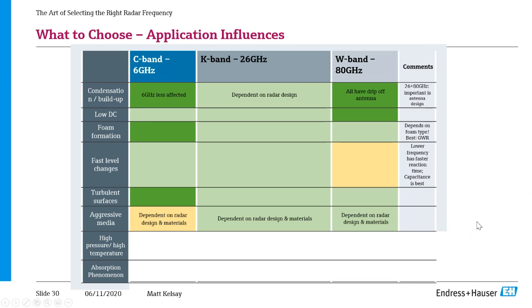When you look at aggressive media, so if you're looking at chemical compatibility, this really depends on the design of the radar and the materials used. So I've got the K-band and W-band as green here, and that's because on those frequency ranges, we have that PTFE style version available.